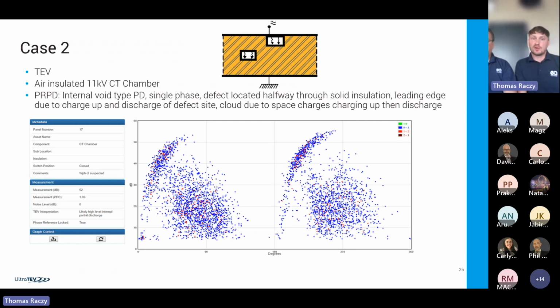Okay, so moving on, we've got an example of discharge collected with a TEV sensor. So this is internal discharge, internal to the insulation. That was collected on an air insulated 11 kV CT chamber. Obviously inside of that chamber there will be CTs. So very typical for internal void type PD, single phase. There's only single phase discharge here, so the defect is probably somewhere halfway through the solid insulation.